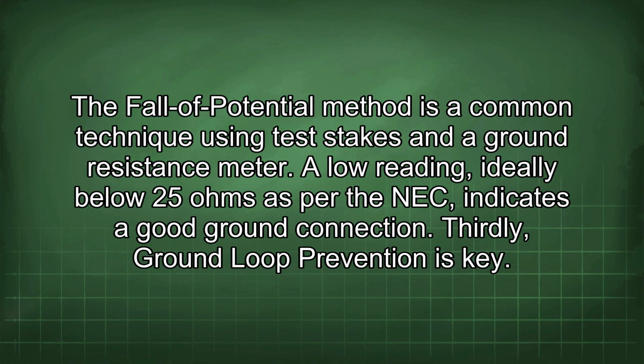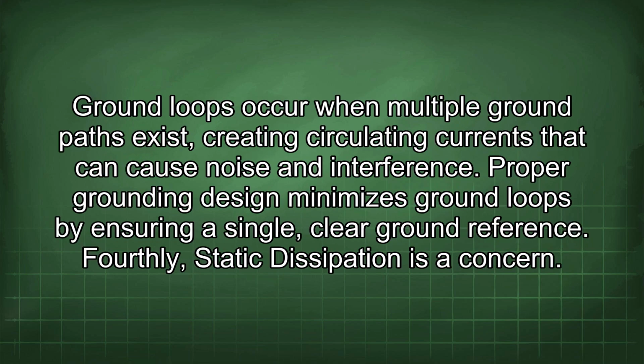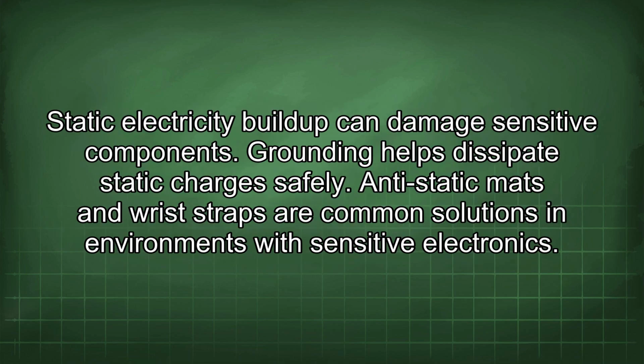Thirdly, ground loop prevention is key. Ground loops occur when multiple ground paths exist, creating circulating currents that can cause noise and interference. Proper grounding design minimizes ground loops by ensuring a single, clear ground reference. Fourthly, static dissipation is a concern. Static electricity buildup can damage sensitive components. Grounding helps dissipate static charges safely. Anti-static mats and wrist straps are common solutions in environments with sensitive electronics.